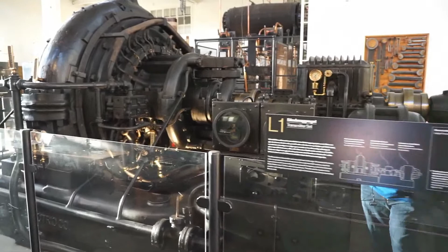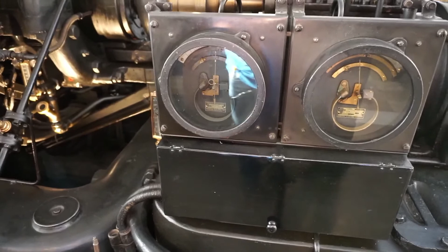We are waiting for the motor to rev up, and then the internal oil pump can handle the oil pressure, and then we get an alarm, and Anders will turn off the auxiliary oil pump. We are now waiting for the amperage to go down. Our target amperage is 75 amps. And we follow that on an ammeter on the panel.